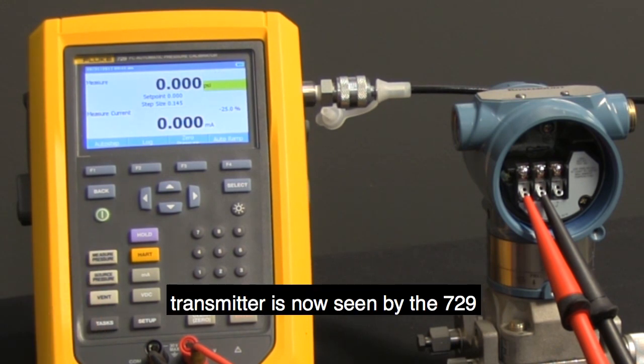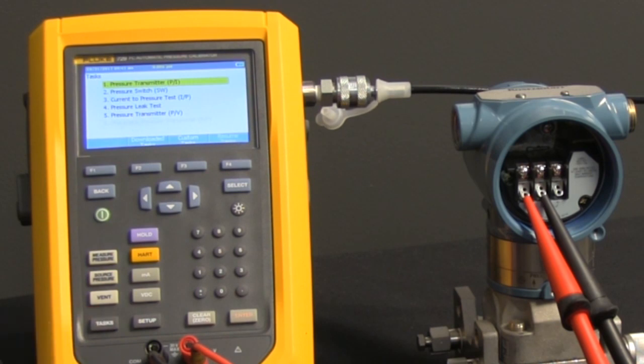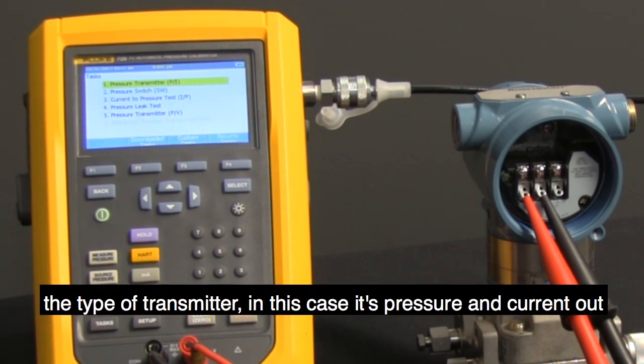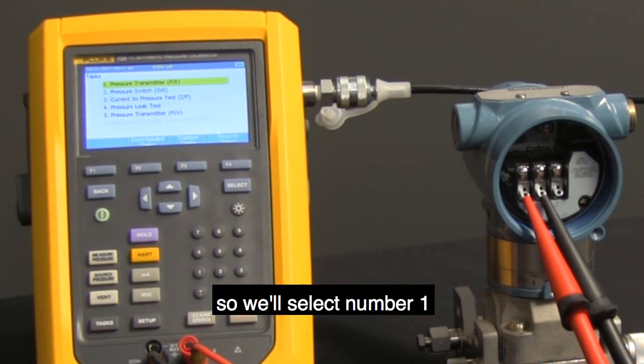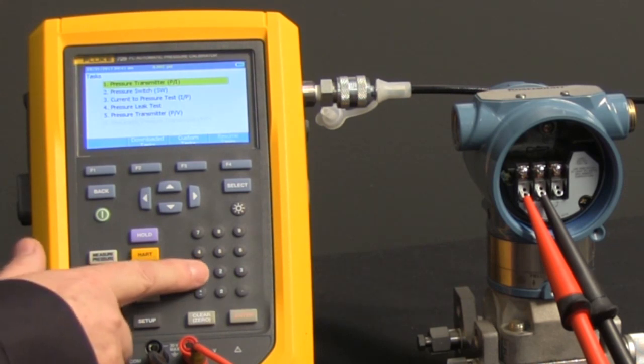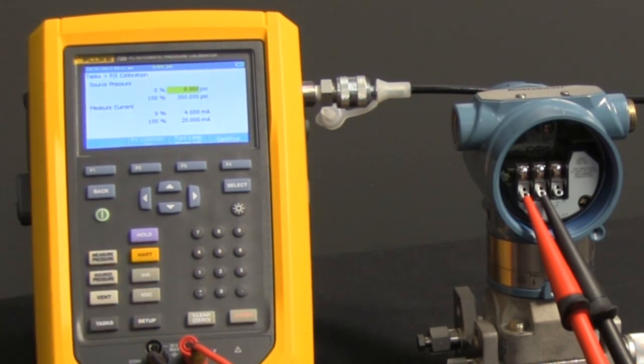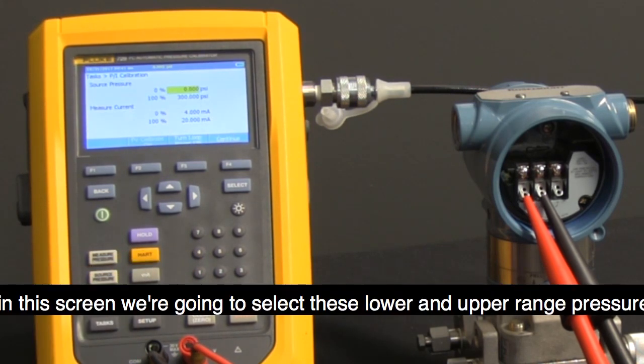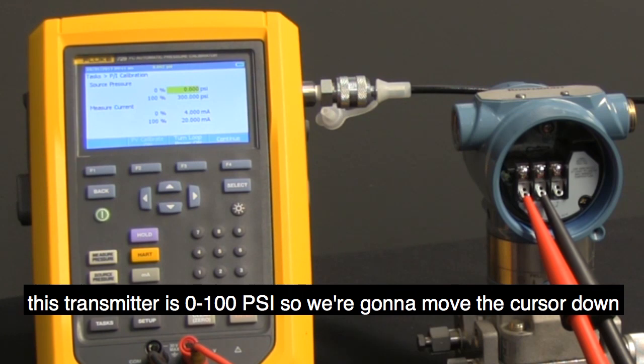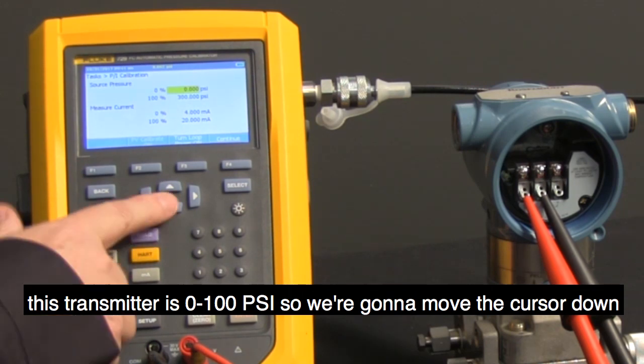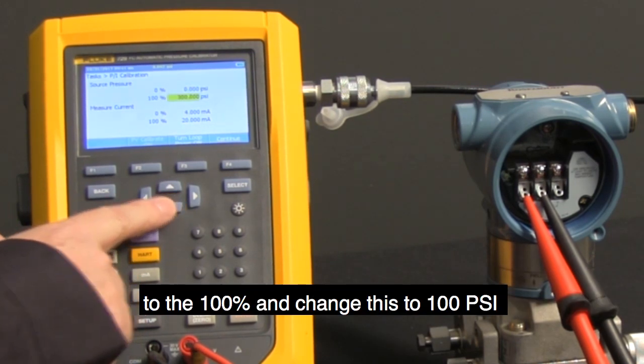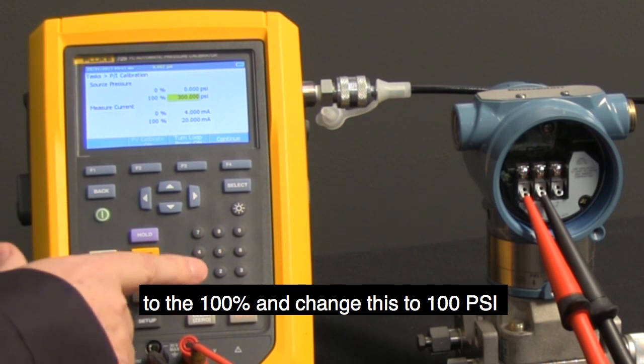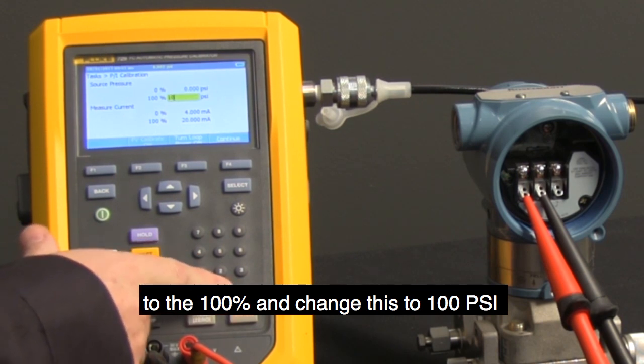Then we're going to go to tasks and select the type of transmitter. In this case, it's pressure in, current out. So we'll select number 1. In this screen, we're going to select the lower and upper range pressure. This transmitter is 0 to 100 psi, so we're going to move the cursor down to the 100% and change this to 100 psi.